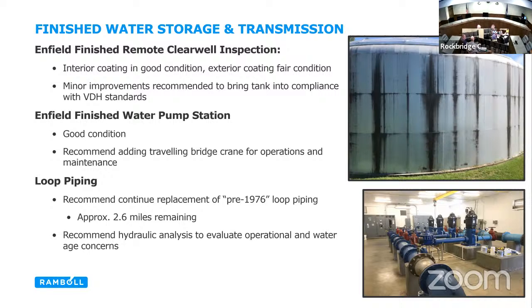With the loop piping, the MSA has started replacing the pre-1976 loop piping. They've replaced about a half a mile recently, but there's approximately 2.5 miles remaining. The recommendation is for the MSA to continue that systematic replacement of aged pipe, which is mostly cast iron or asbestos cement, with some possibly ductile. It's getting to that 50-year mark in the ground, which is the point where you need to evaluate and consider replacement before breaks occur.